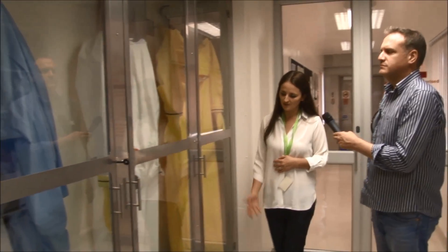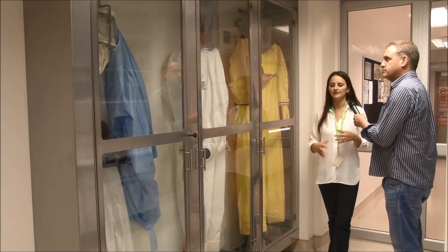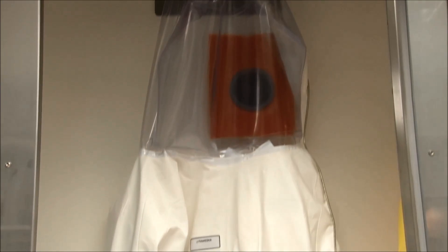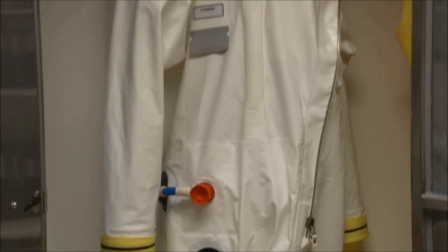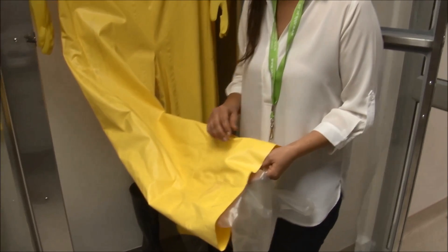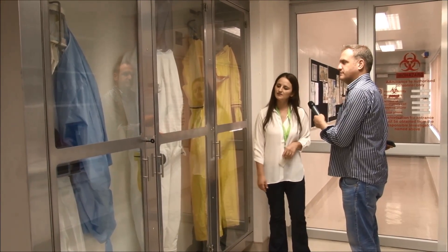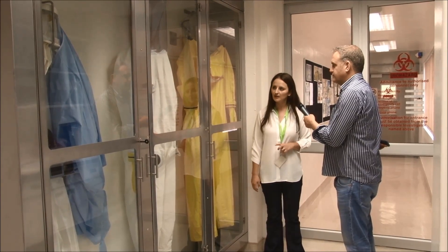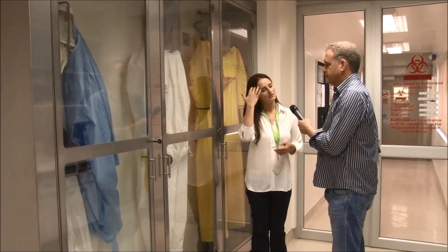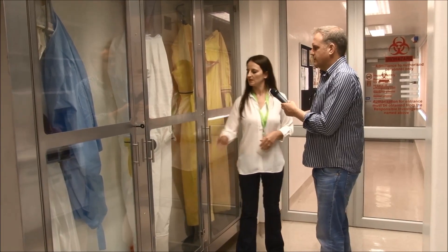If you want to work in a level 4 laboratory, you have to wear the right protective equipment. The laboratory itself provides what we call a biocontainment bubble — there's lots of engineering that drives the environment as well; it's not just the room. We use fully enclosed plastic biosafety suits. When you zip these, they're airtight. You check the suit for any holes before use, and you sign off that you're happy to use it every time. Once the suit is on, you quickly hook up to a breathing air supply — there's a tail on the suit you connect to air supply coils distributed throughout the laboratory, suspended from the ceiling. You hook in, hook out, and move through the lab, and the suit puffs up with breathing air.